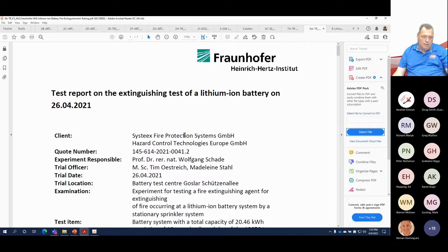This is another test, and I want to first show you, because one of the questions we get asked is, have you run your UL 9540 and 9540A test? And the answer is no. We've reviewed 9540 and 9540A. 2 weeks ago, we drove up to Indiana and reviewed it with Battery Innovation Center, and they all agree, and UL agrees, it's a testing of the thermal runaway properties of the battery energy storage system and not really a fire suppression test. So we are working with them to create a fire suppression test.